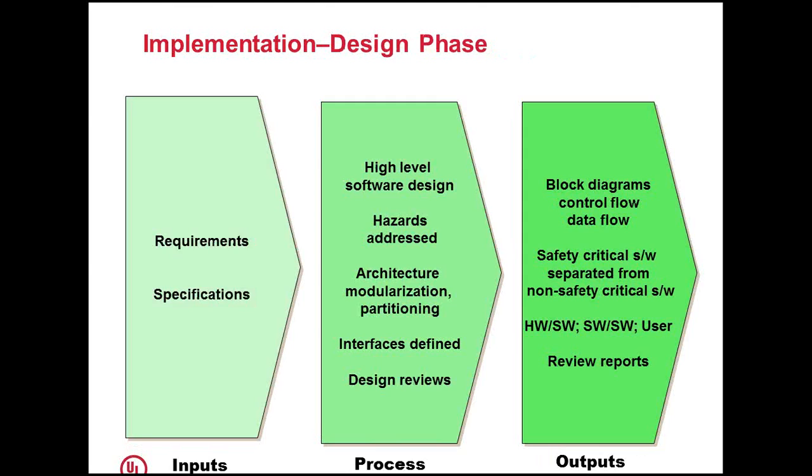Design phase: the output from the requirement phase is taken here, that's the requirement specifications. You do a high-level software design. You address all the hazards by means of your design methodologies. You do the architecture, modularization, partitioning, interfaces, and also the reviews. The deliverables at this phase are block diagrams, control flow, how the data flows, and how the data interfaces are there. Which are safety critical software, which are non-safety critical, what hardware-software interface is there, what software interface is there, what user interface is there. All those things come into this phase.